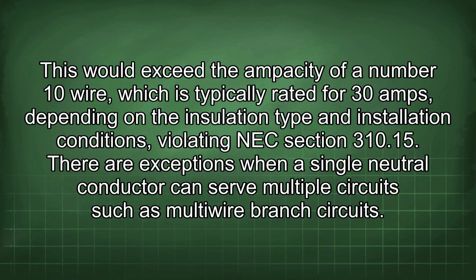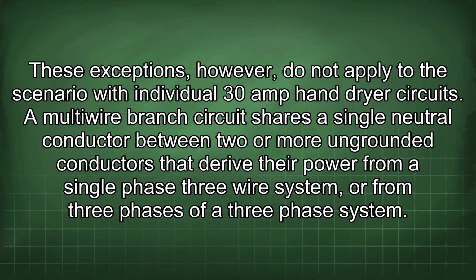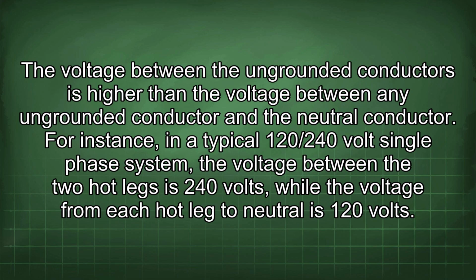There are exceptions when a single neutral conductor can serve multiple circuits, such as multi-wire branch circuits. These exceptions, however, do not apply to the scenario with individual 30 amp hand dryer circuits. A multi-wire branch circuit shares a single neutral conductor between two or more ungrounded conductors that derive their power from a single-phase 3-wire system or from 3 phases of a 3-phase system. The voltage between the ungrounded conductors is higher than the voltage between any ungrounded conductor and the neutral conductor.